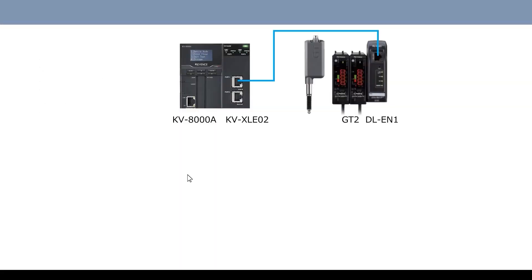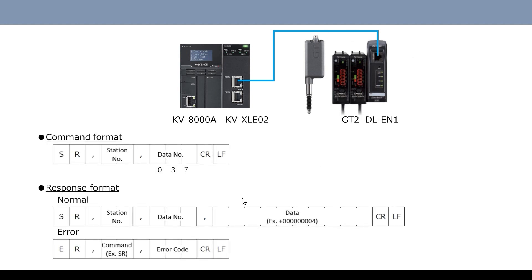Let's communicate with the communication unit called DLEN1 and read the PV value of GT2 series. The device configuration is as follows: KVXLE02 and DLEN1 are connected by LAN cable, and two GT2s are connected to DLEN1. Let's use the SR command to read the PV value. Specify the station number of the sensor amp to read and the data number of the data to read. The data number of PV value is 37.